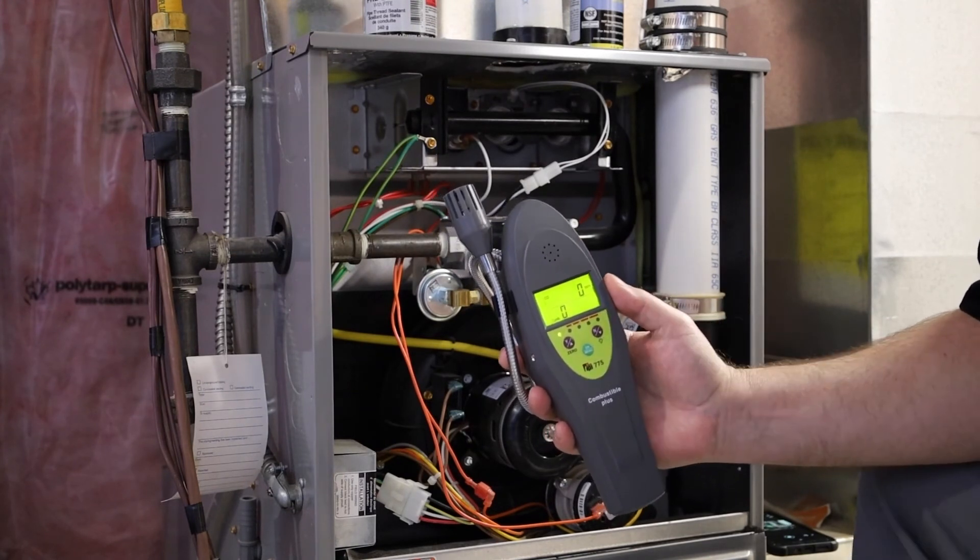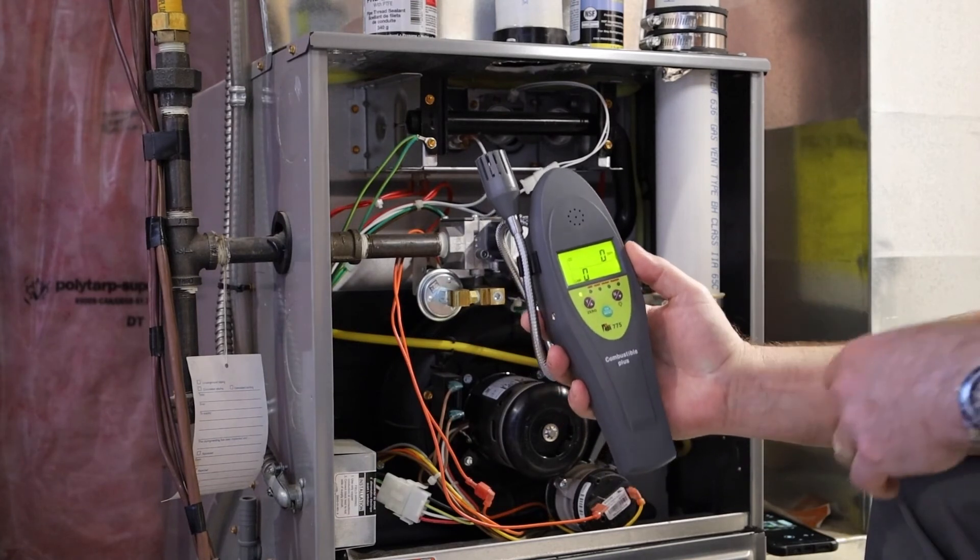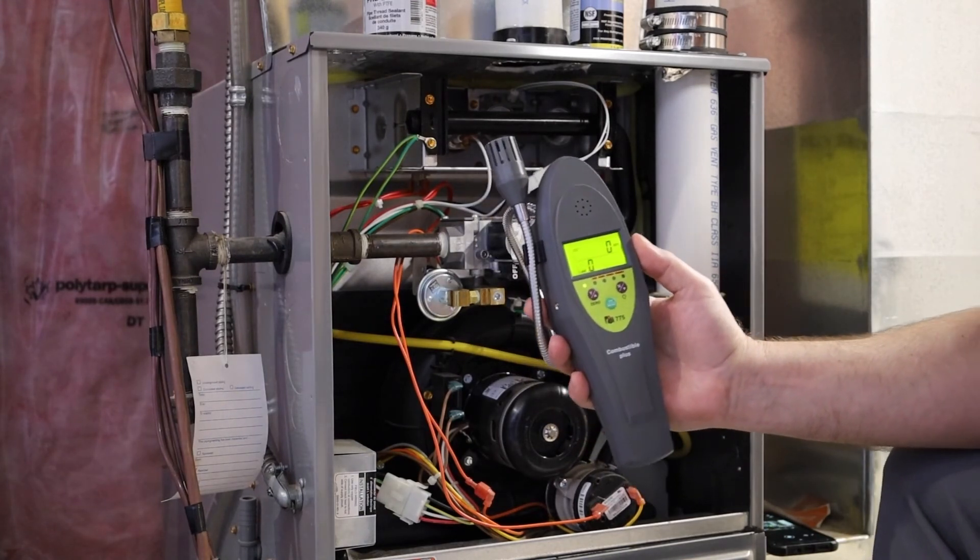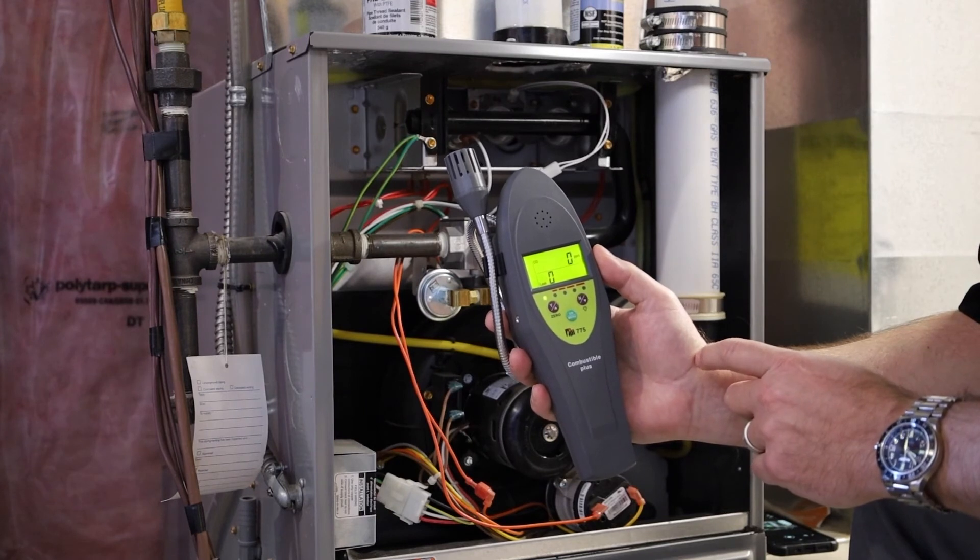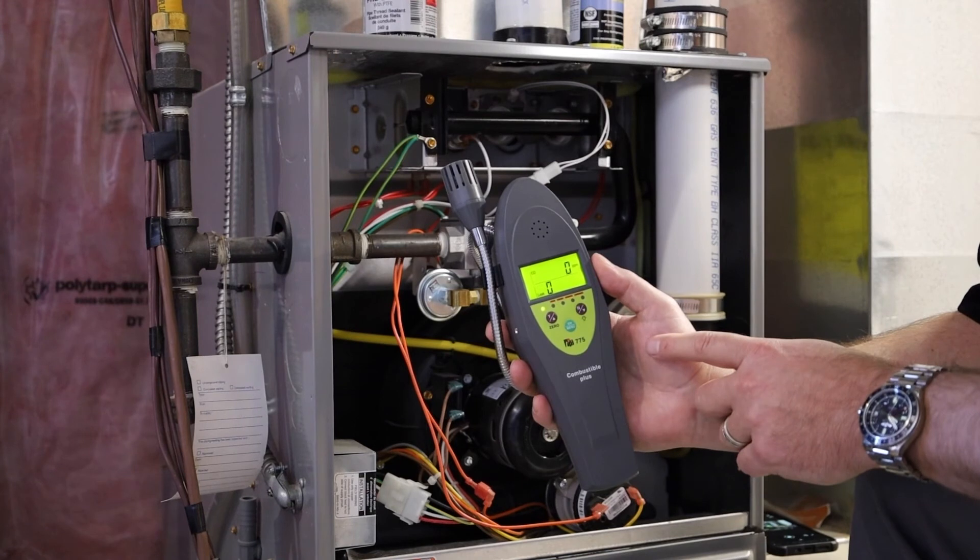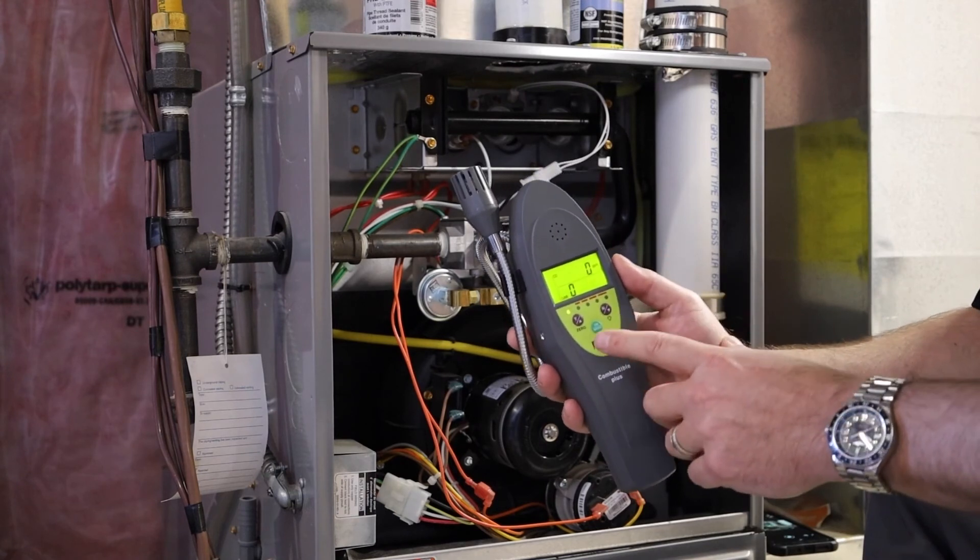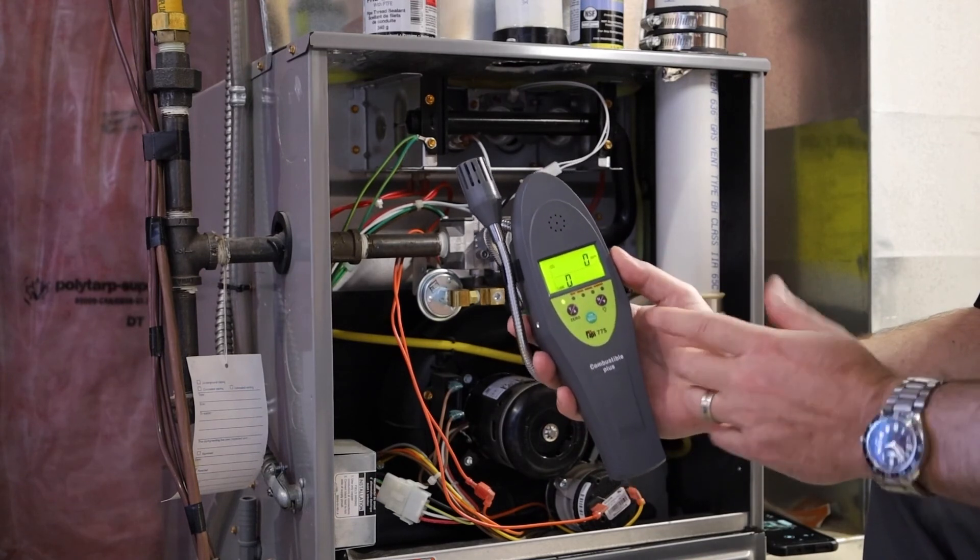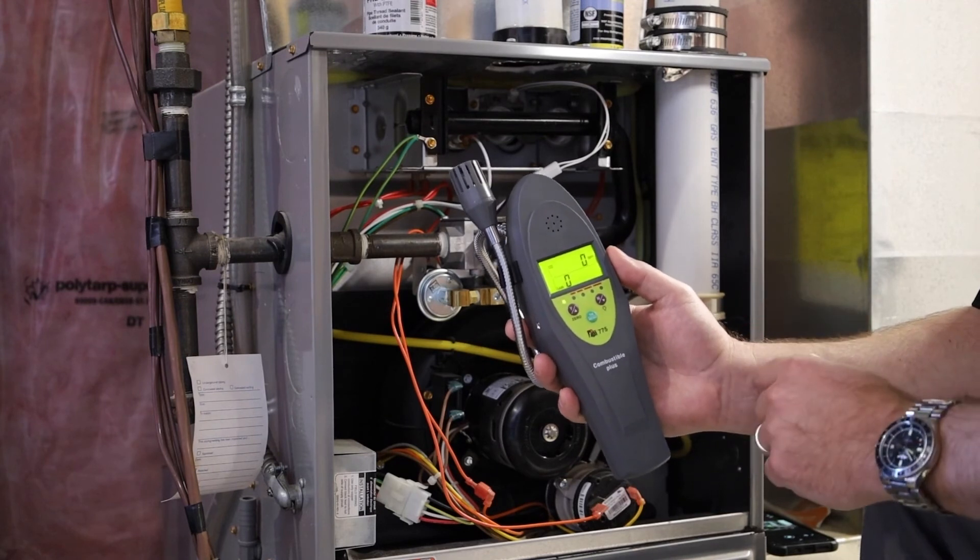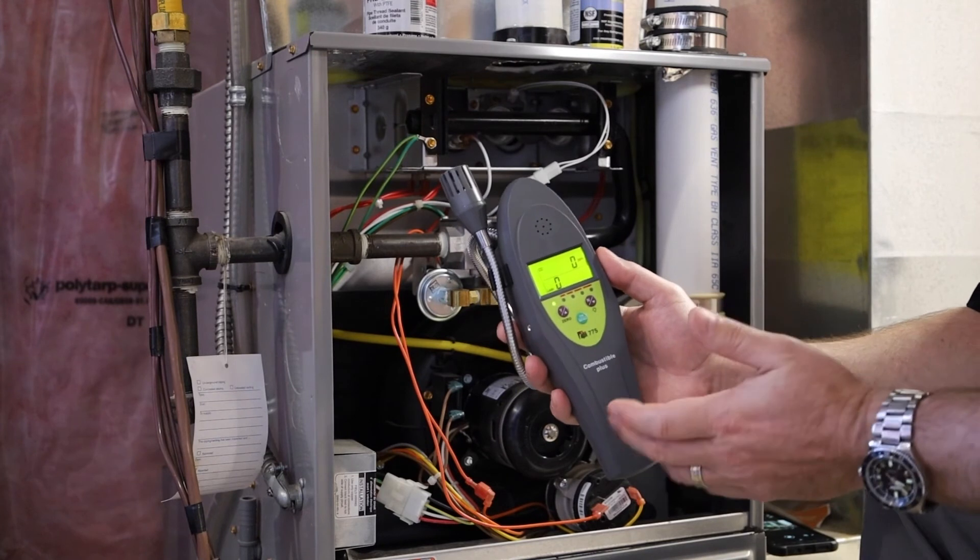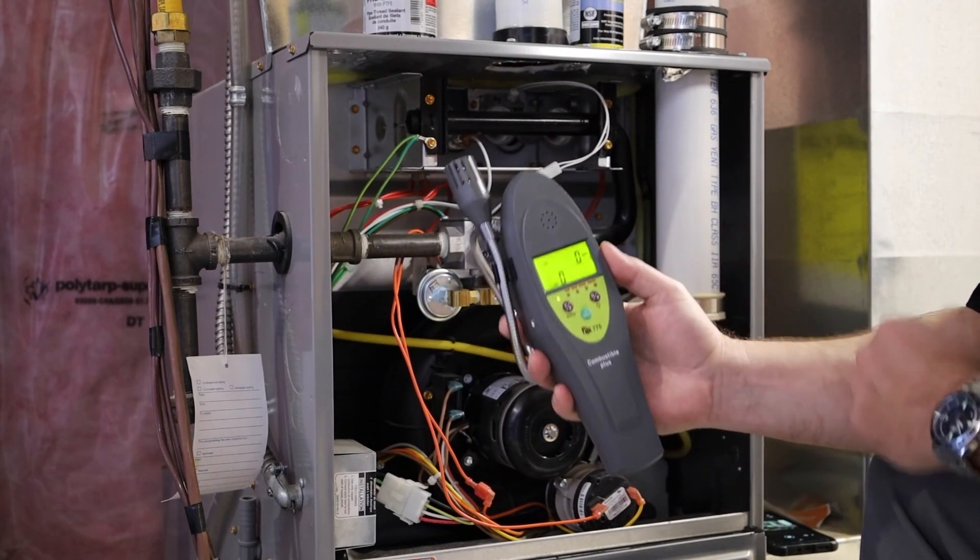So down here, you've got your leak sensor that will go all the way up to 50,000 parts per million. But it's in stages. So it's going to go one, two, three, and indicate what the level is. If it's indicating number one, the leak's going to be between 100 and 500 parts per million. If it goes up to number two, it's going to be up to 1,000 ppm, and then three is 1,500 and so forth. So you can also set alarms for this. We've preset this CO alarm from the factory at 30 parts per million. So it's going to give you an audible and a visual alarm if your ambient CO rises above that. And in a residential application, 30 ppm is a great place to have it at. But it's going to display all the way down to one part per million.